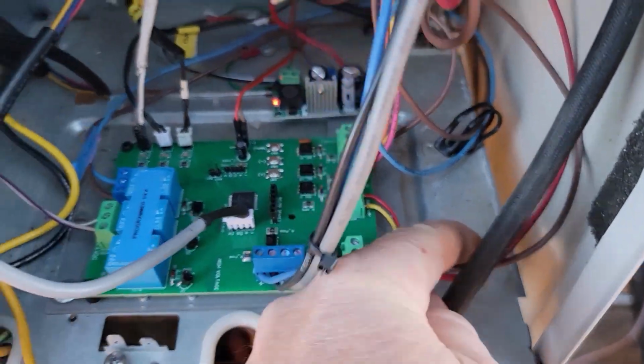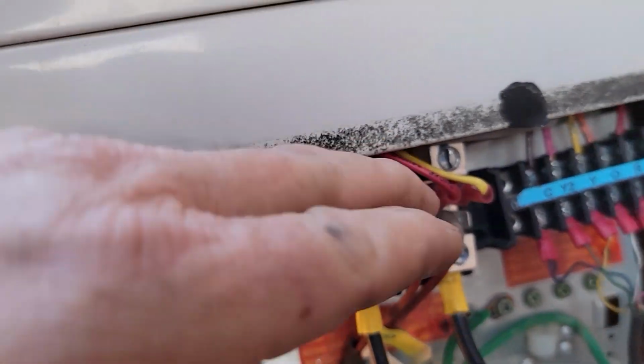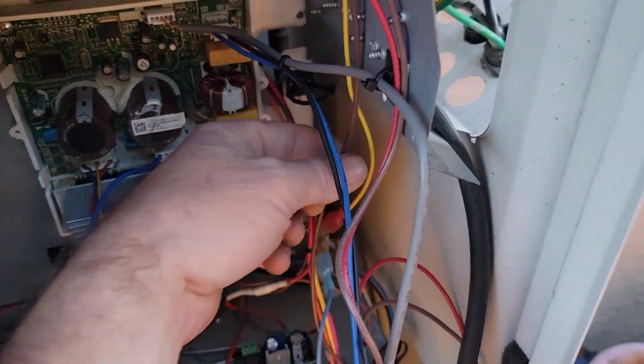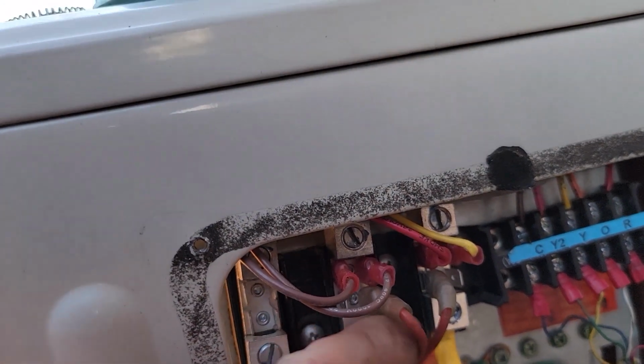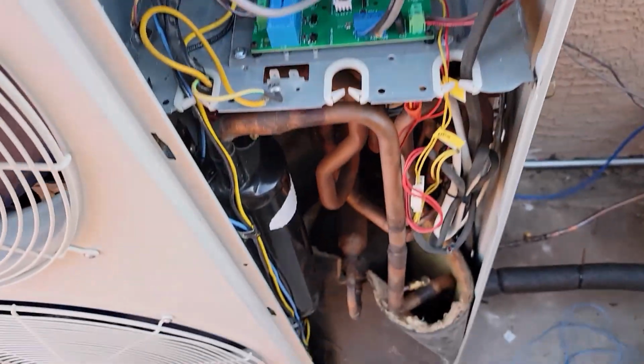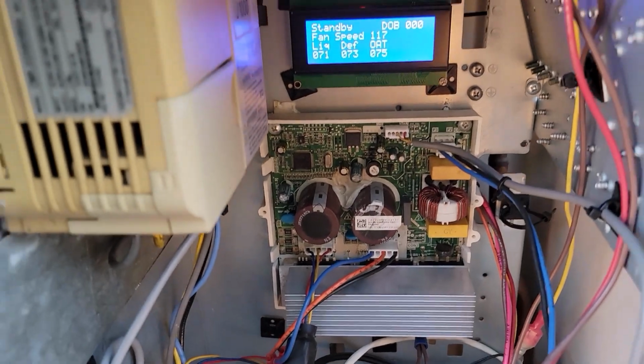So high voltage right here - these 2 legs, brown and red. Brown and red, then brown and yellow is powering the reversing valve. There's 2 other power legs right here - those go down to the crankcase heater. So now it should be ready for high voltage.